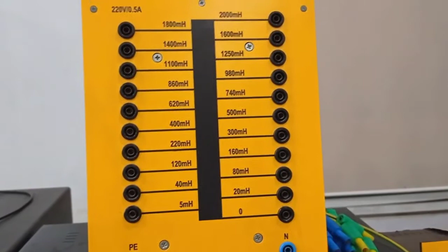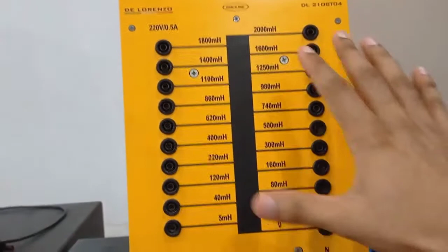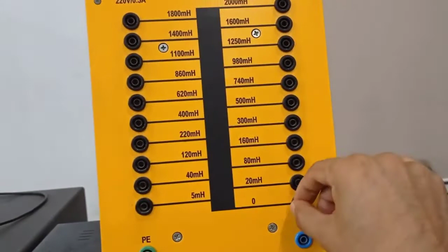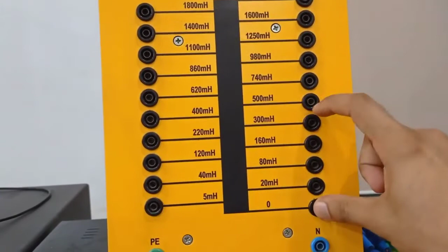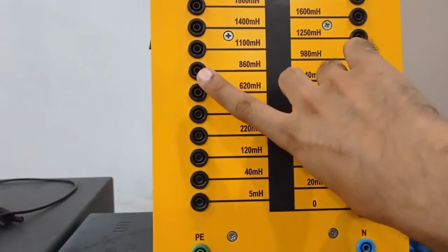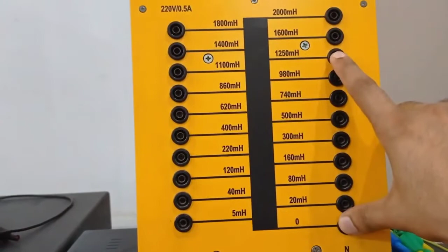In the second part of experiment number 6, students will calculate the value of the resonating inductance that is to be connected between neutral and ground. And once they have calculated the value, it could be taken from these different values of inductor by using this 0 point and the required value. For example, if the required inductance value is 500 millihenry, then these 2 points will be used. If the required inductance value is 860 millihenry, then these 2 points will be used. And so on. If 1250 is required, then these 2 points will be used. Students will use the value of inductance according to their calculation.